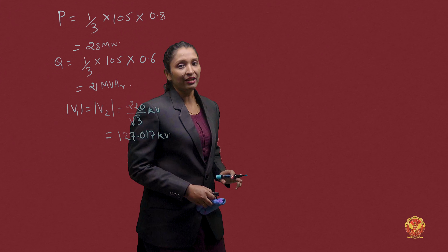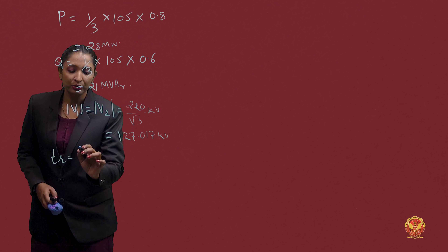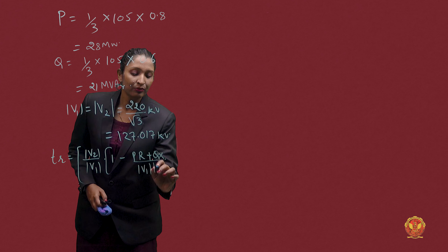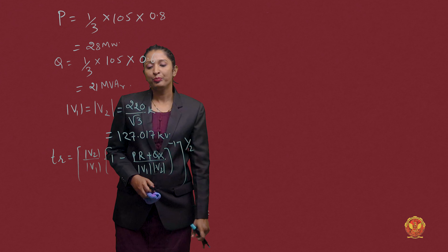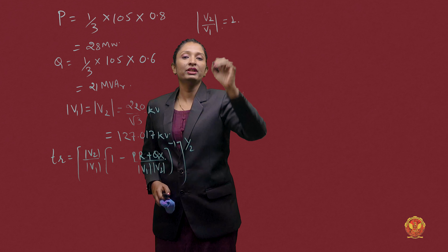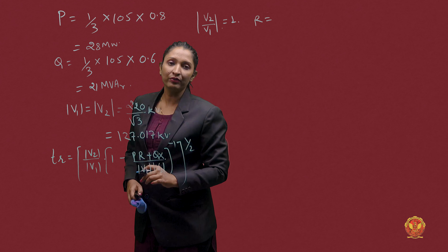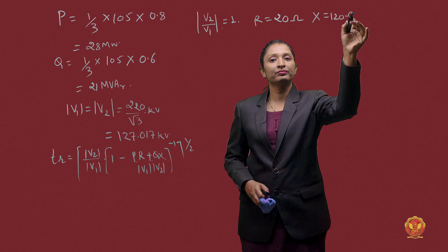We derived the tap-setting equation in the previous lecture — refer to it for the derivation. The equation is: Ts equals the magnitude of V2 divided by V1, multiplied by the inverse of the quantity [1 minus (PR + QX) divided by V1·V2], all under a square root. Here, the magnitude of V2/V1 is 1. The impedance is 20 + j120 ohms, so R equals 20 ohms and X equals 120 ohms. We now know P, Q, R, X, V1, and V2.